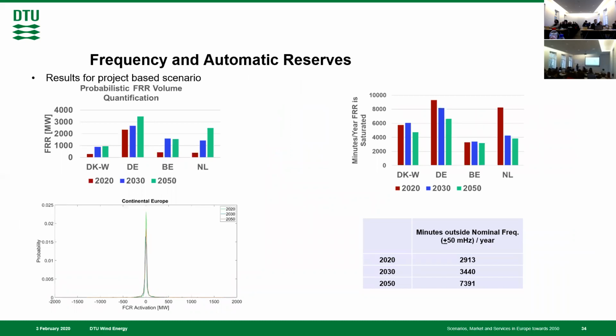What we did here is quantify the requirement of restoration reserves. In practice, you'll also have imbalances caused by other sources, like load imbalances, grid faults, and things like that, which can reduce or increase the overall imbalance. They're not necessarily correlated—some are correlated if it's temperature-dependent load driven by the same weather, but not everything is correlated, so that's a difficult problem in itself.